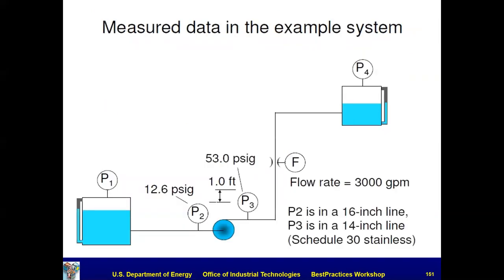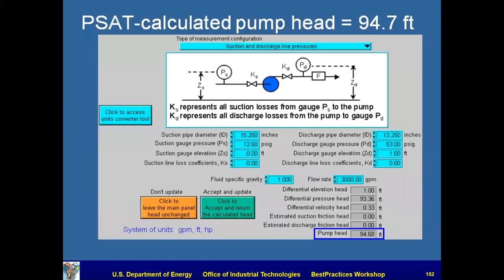Okay, measured data. So you can go up to the pump and take these measurements. Say we use our strap-on ultrasonic flow meter, or maybe the plant has a flow meter. So by hook or crook, we come up with a flow we have some confidence in at 3,000 GPM. P2 is the suction pressure, and it's in a 16-inch line. And P3, and you see the pressures there, it's in a 14-inch line, schedule 30 stainless. The elevation difference between the gauges is 1 foot. And so I've got 53 on the discharge and 12.6 on the suction. So bingo, put that in the PSAT pump head calculator, and I get 94.7 feet.